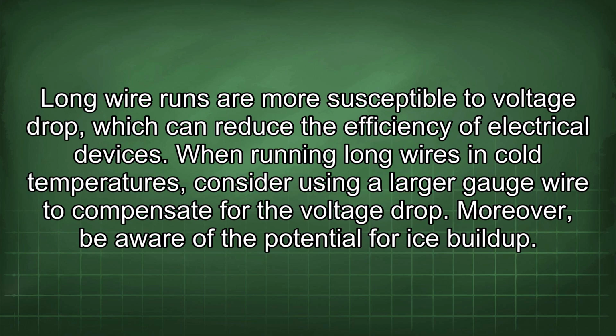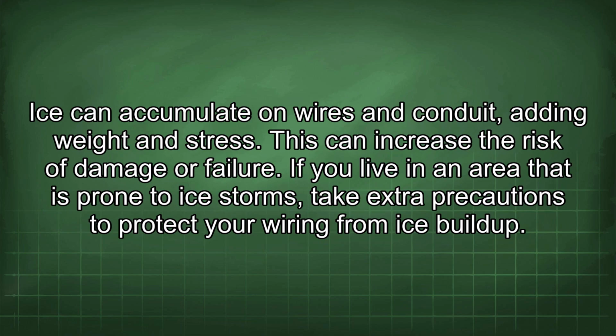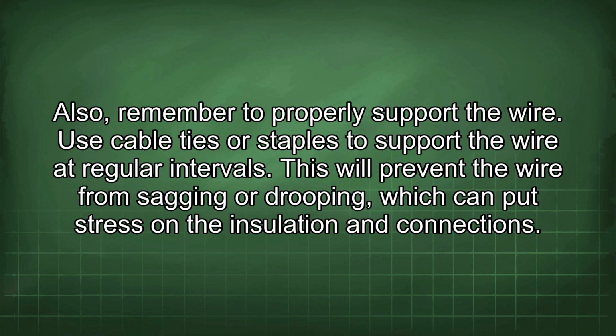Long wire runs are more susceptible to voltage drop, which can reduce the efficiency of electrical devices. When running long wires in cold temperatures, consider using a larger gauge wire to compensate for the voltage drop. Moreover, be aware of the potential for ice buildup. Ice can accumulate on wires and conduit, adding weight and stress. This can increase the risk of damage or failure. If you live in an area that is prone to ice storms, take extra precautions to protect your wiring from ice buildup. Also, remember to properly support the wire.